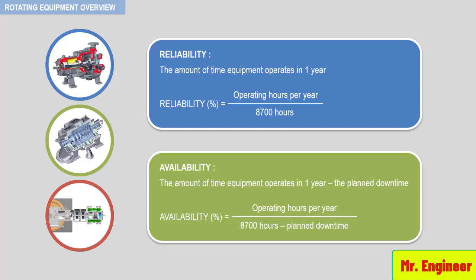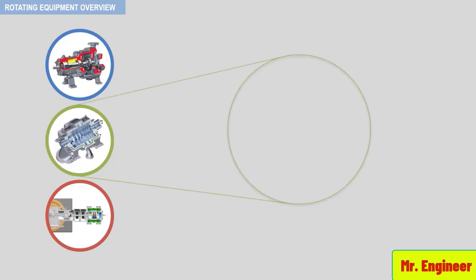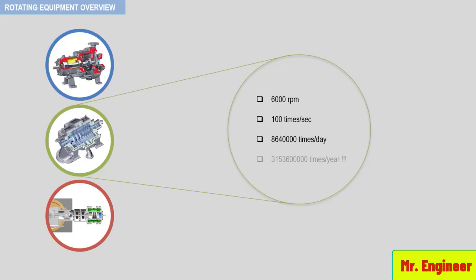To better illustrate this and put things into perspective, let's take a look at the following figures, which represent typical facts concerning a centrifugal compressor. A typical centrifugal compressor running at 6,000 RPM rotates at 100 times per second and 8,640,000 times per day. The revolutions per year are quite impressive — and all this is done on an oil film of less than 1/1000 of an inch.